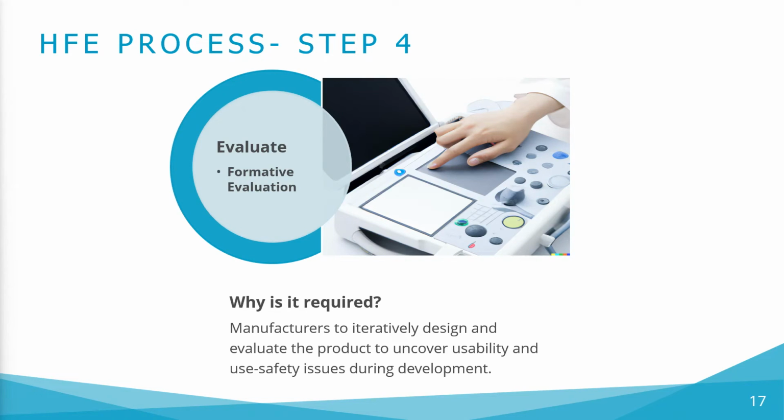Why is it required? The FDA and other regulators expect manufacturers to iteratively design and evaluate the product to uncover usability and use safety issues during development. Each evaluation identifies findings, for example, use errors induced by design flaws that warrant further risk mitigation, that is, design changes.